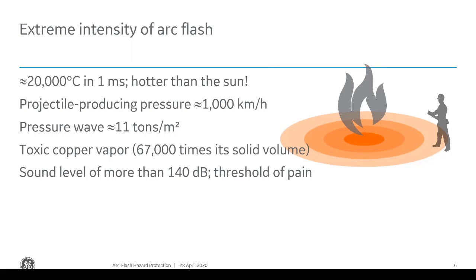Arc flash has some interesting properties. The temperature core of an arc can reach up to 20,000 degrees C or 35,000 degrees F in about 1 millisecond, a very, very short period of time. Just for some perspective, the surface of the sun's temperature is 5,000 degrees C. So it's basically on the low end about 4 times hotter than the sun, and it can be higher than that depending on the arc flash energy. Projectiles created by arc flash can fly at about 1,000 kilometers per hour, so very high speed, and it can cause a lot of damage.